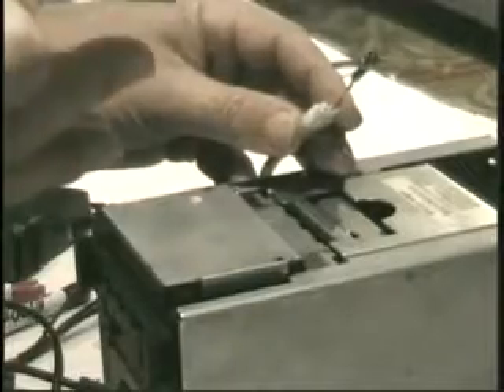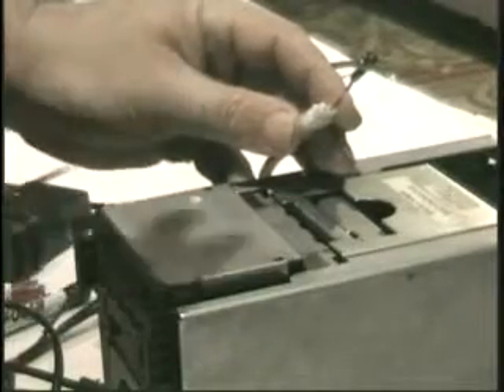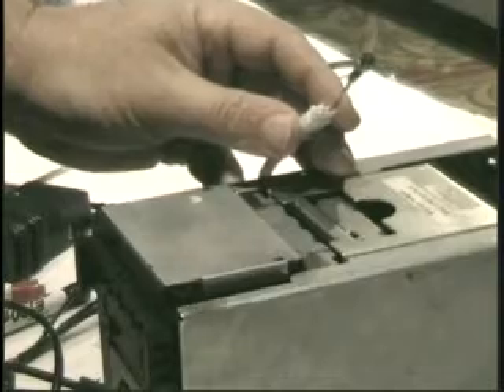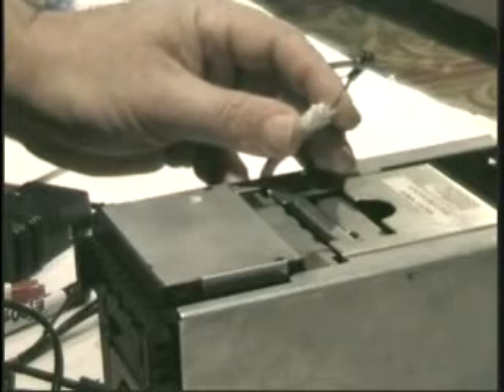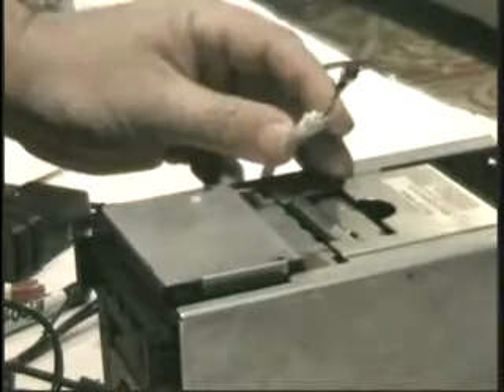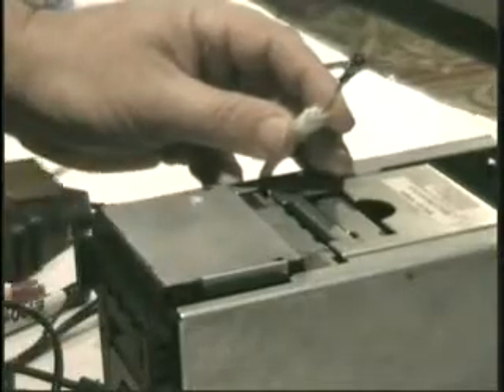Either the LED is burned out or the phototransistor's gone bad. They're electronic components; they fail at times. If it does, what you're going to see is that light's on even though the lid is closed and you don't have anything slid in there.